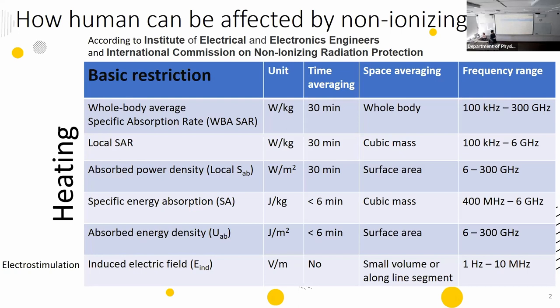There are many quantities related to heating that you need to calculate to evaluate compliance with set standards. The first is the Whole Body Average SAR. As you could know from the name, it's the amount of power dissipated by your body as a whole. You calculate all the power dissipated by your body and divide it by your mass. Because heating is a slow process, you need to average this over 30 minutes in cases of non-constant radiation.